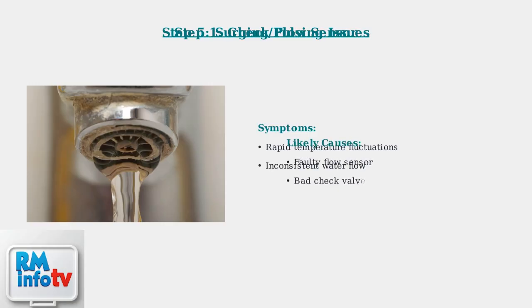If you experience surging or pulsing water temperatures, where the temperature fluctuates rapidly, this typically indicates a faulty flow sensor or check valve. This symptom requires immediate attention.